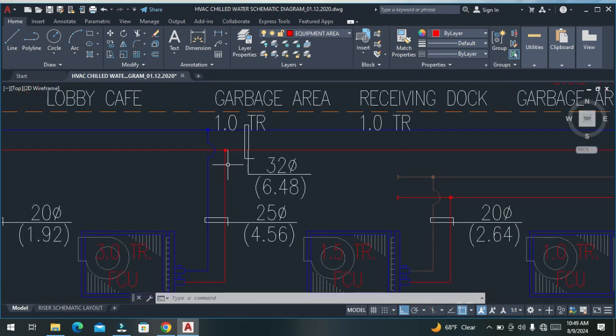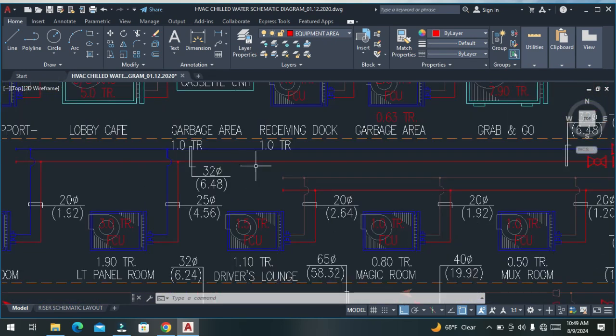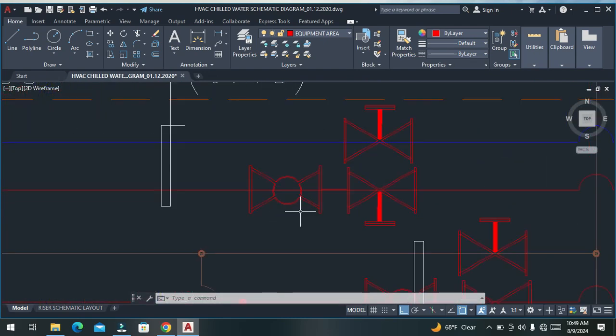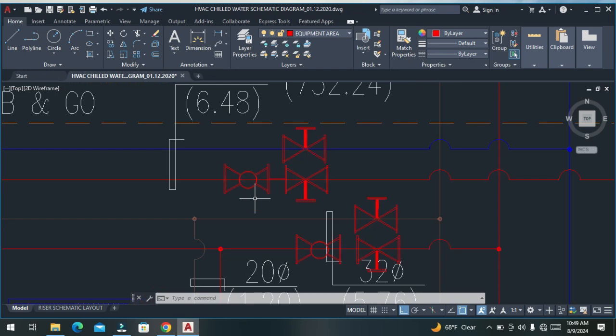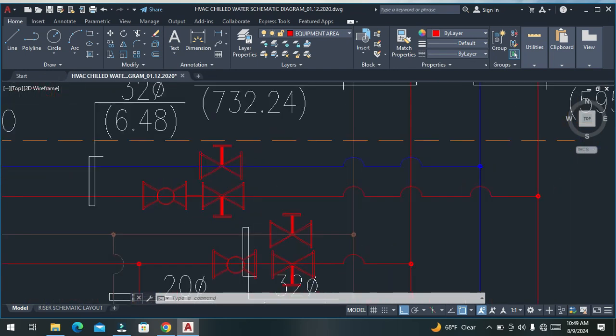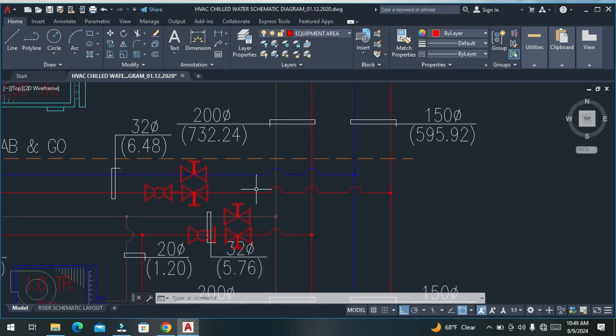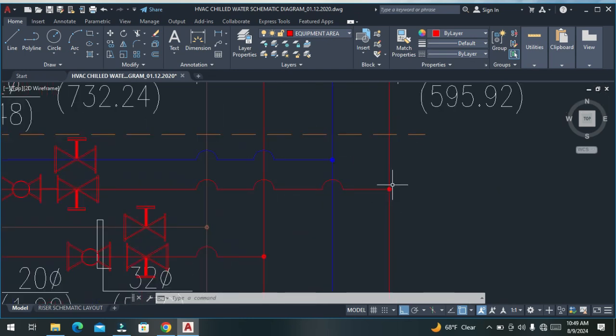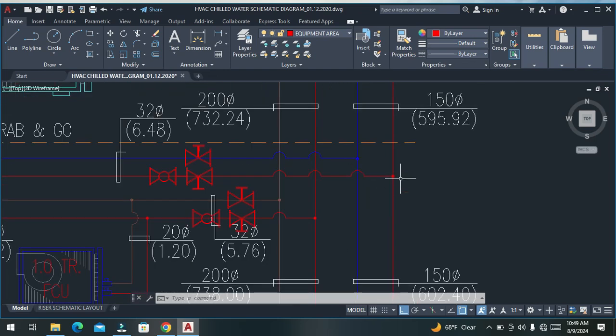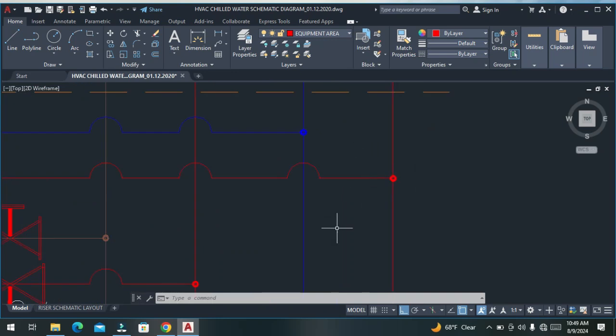Now again this is the return line. Over here again we have a balancing valve or actuator, then again a valve in the return line, and it goes to the riser. This is the chilled water supply riser and this is the chilled water return pipe. From here it goes to the unit, and from here it will return over here. There is always a temperature difference, but it should not be more than 5 degrees Celsius delta T, even in 100% load condition at the chiller.